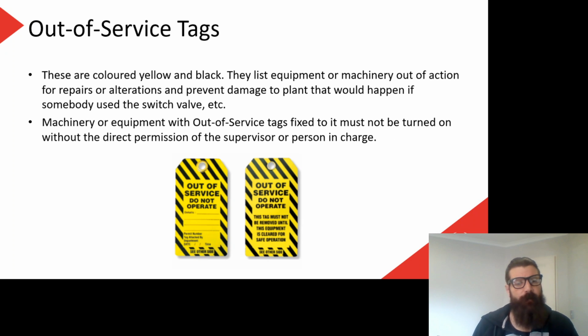So having a look at our out of service tags, these ones are yellow and black. They list equipment or machinery out of action for repairs and prevent damage to plant that would happen if somebody used the switch or valve, etc. So this might not be personal danger, but if I've left the machine in bits and somebody switches it back on and bits are going to go flying everywhere and destroy that machine, I need to have an out of service tag. Machinery or equipment with an out of service tag fixed to it must not be turned on without the direct permission of the supervisor or person in charge. And then it makes sense that wherever I attach that out of service tag must be where somebody would go and turn it on. There's no point in me attaching a tag somewhere else and then somebody could come and switch that thing on without seeing my tag.